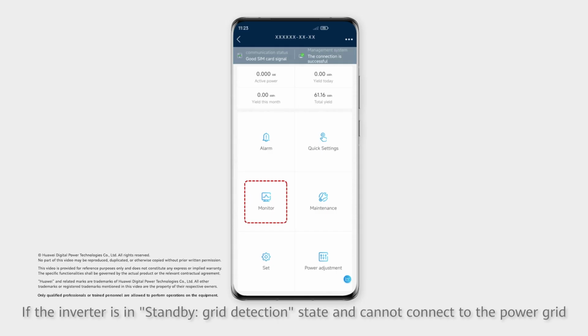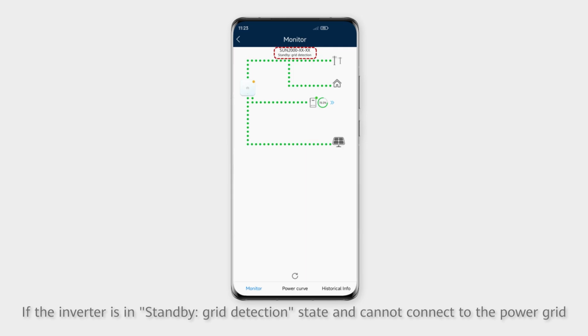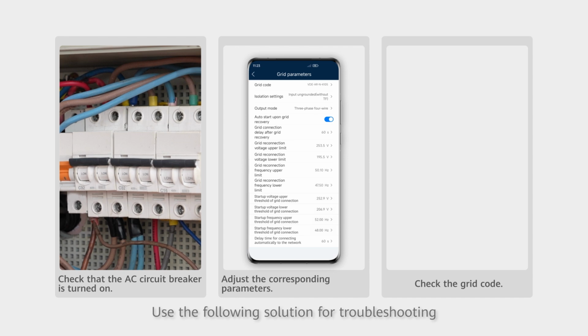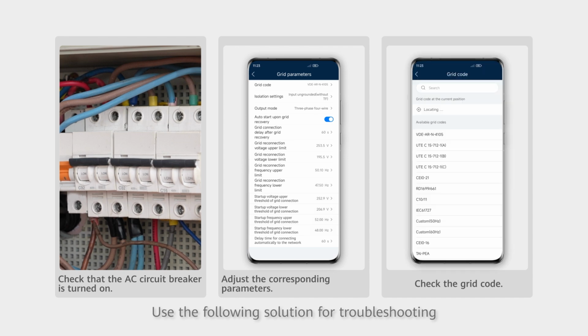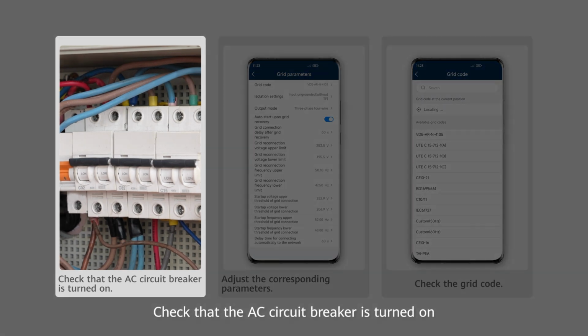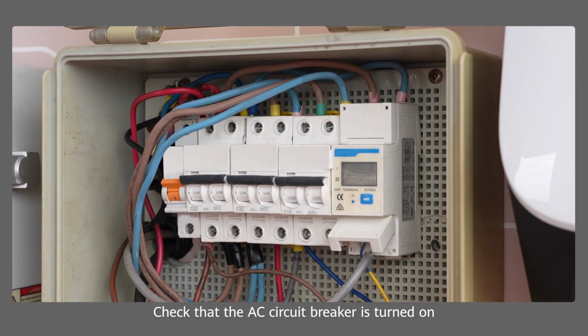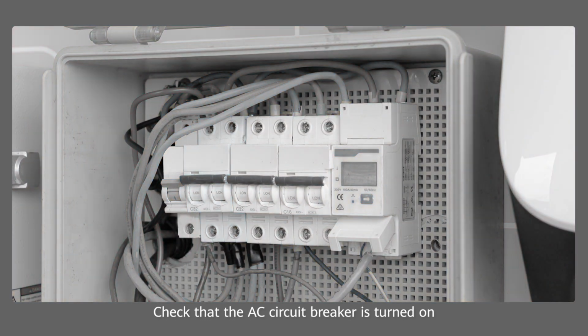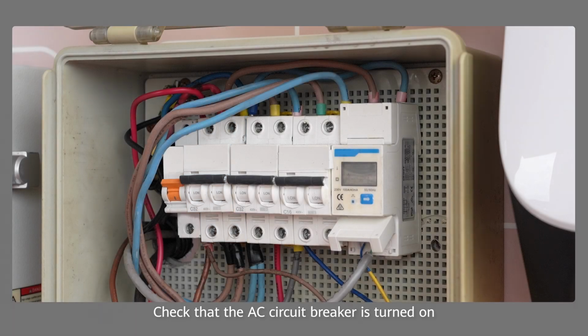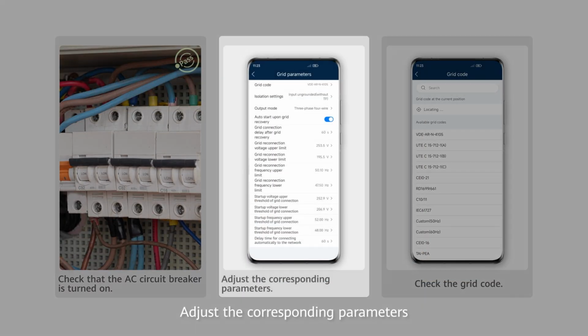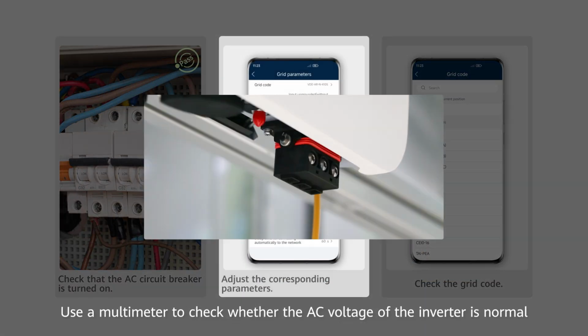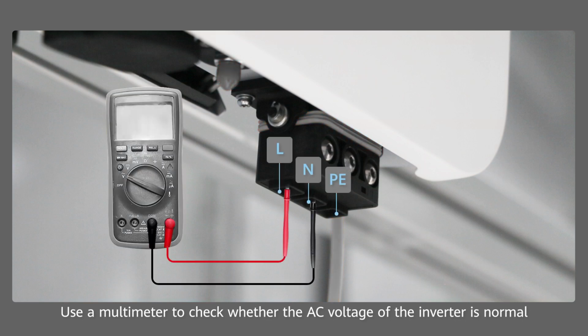If the inverter is in standby, grid detection state and cannot connect to the power grid, use the following solution for troubleshooting. Check that the AC circuit breaker is turned on. Adjust the corresponding parameters. Use a multimeter to check whether the AC voltage of the inverter is normal.